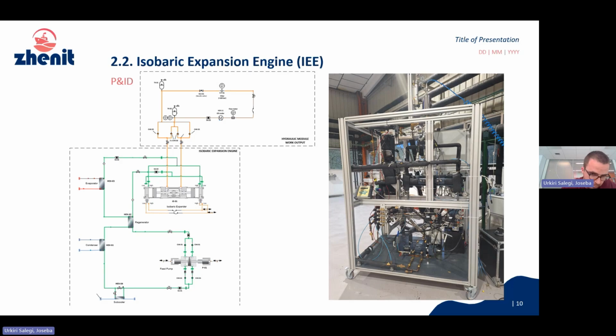After that, when the refrigerant is expanded at low pressure, it arrives at the regenerator. Here it decreases its temperature, arrives at the condenser, and passes to liquid state. And lastly, we have the subcooler. The subcooler is responsible for decreasing the temperature of the liquid refrigerant, and it's very important because it is the main component preventing cavitation in the feed pump. If the refrigerant is colder, it's easier to prevent this phenomenon.